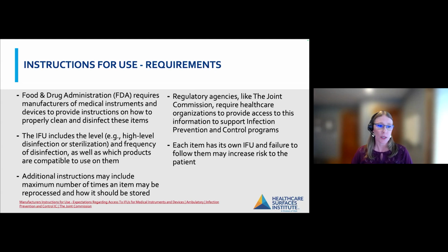So the IFU needs to tell the user the level and frequency of disinfection. I'll go into the Spaulding classification in just a moment, but the level of disinfection might be something like high-level disinfection or sterilization. They also tell us which products are compatible to use on them.